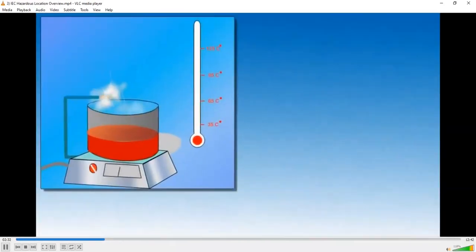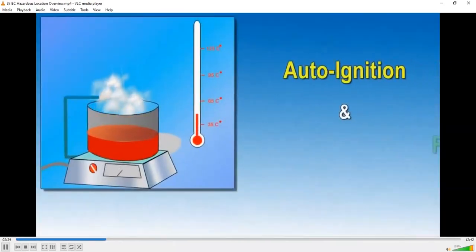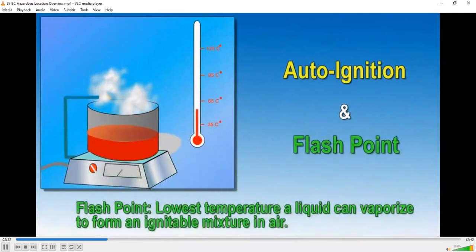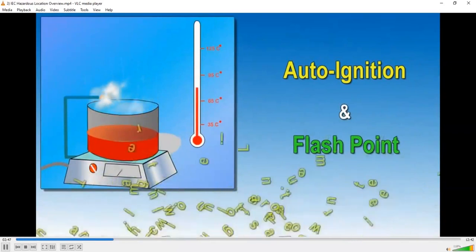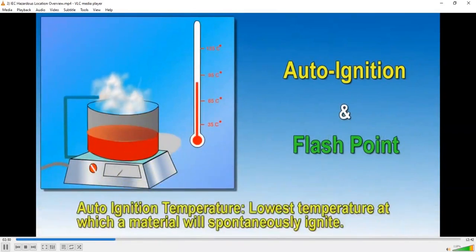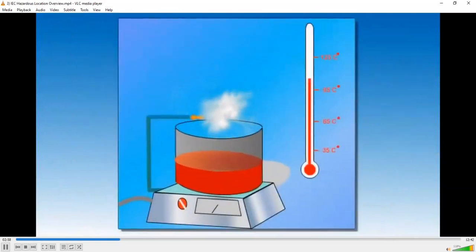In addition to the explosive limits, each hazardous material will have an auto-ignition temperature and a flash point. The flash point is the temperature at which the material will generate sufficient quantity of vapor to form an ignitable mixture. As the liquid is heated and reaches the flash point, ignition could occur. The auto-ignition temperature is the lowest temperature at which a combustible material will spontaneously ignite in a normal atmosphere. In this example, we have the heating of a combustible liquid. Explosive vapors are created as the material reaches the explosive limits, creating the flash point. If the general atmosphere is increased to the auto-ignition temperature, fire or explosion will occur.